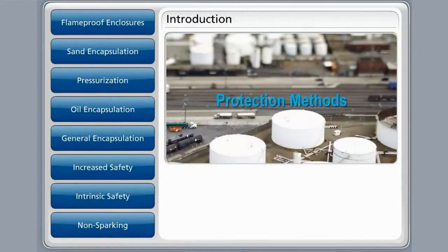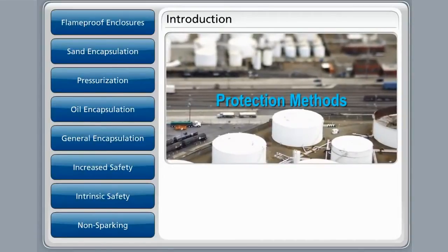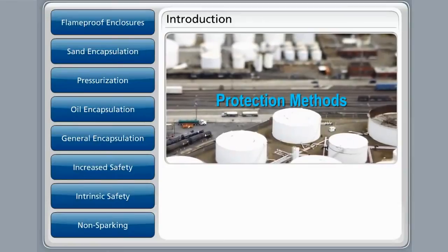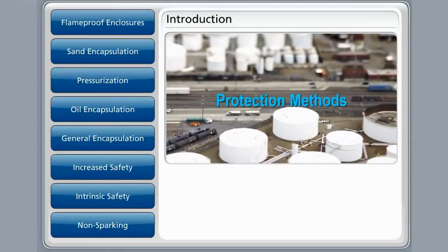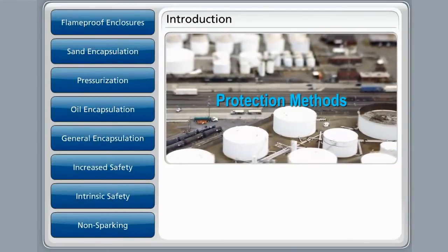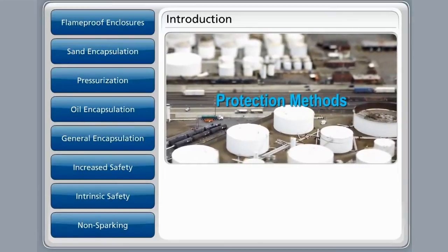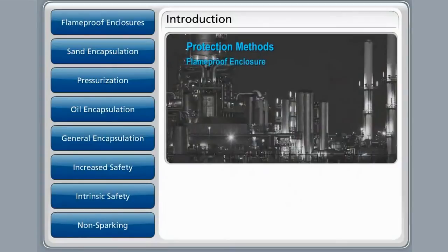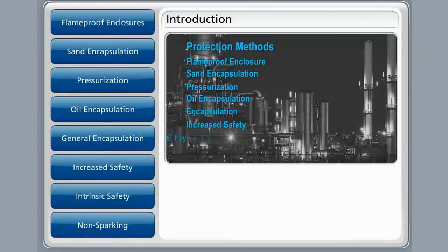Let's take a look at each method of protection and its general application. To ensure safety, equipment is placed in protective level categories. Category 1 is the highest safety level, making category 3 the lowest risk and safety level. The general eight protective methods are: flame-proof enclosures, sand encapsulation, pressurization, oil encapsulation, general encapsulation, increased safety, intrinsic safety, and non-sparking.